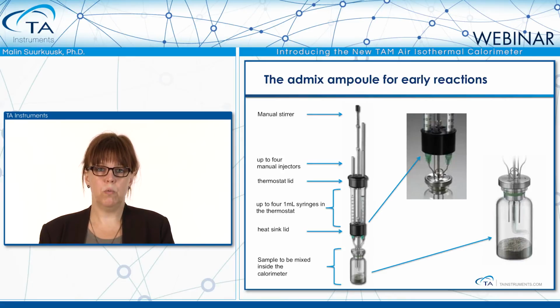The syringes, which could be 1 up to 4 1 milliliter syringes, sit in the thermostated part of the thermostat, and then you have a thermostat lid above the syringes. In this way, the liquid you're injecting into your sample is at the same temperature as the sample inside the calorimeter. Above the thermostat lid, we have the manual injectors, where you can push down to inject the sample into the ampule. And in this picture, we have a manual stirrer, and that can move up and down and also rotate, so you can get a very good mix of a cement sample. The motor mixer will just be rotational stirring if you put the motor on the top. And the height of the stirrer can be modified to fit that particular sample.